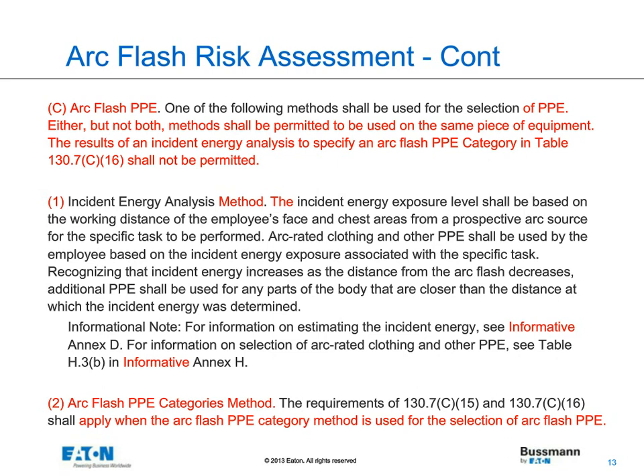Many people often wonder what's the best method, either the analysis method or the PPE method. And quite frankly, it depends upon where you're at as far as complying with the OSHA requirements. In many cases, you're forced to use the category method because you have to start somewhere. And eventually you might go to the analysis method, but the category method is a great way to start getting compliant with the OSHA requirements.